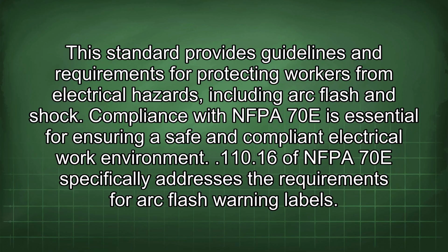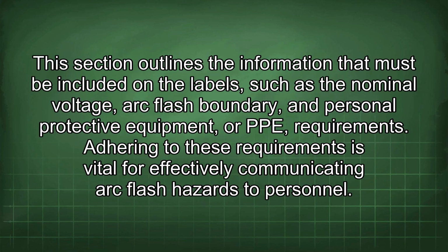110.16 of NFPA 70E specifically addresses the requirements for arc flash warning labels. This section outlines the information that must be included in the labels, such as the nominal voltage, arc flash boundary, and personal protective equipment, or PPE, requirements. Adhering to these requirements is vital for effectively communicating arc flash hazards to personnel.